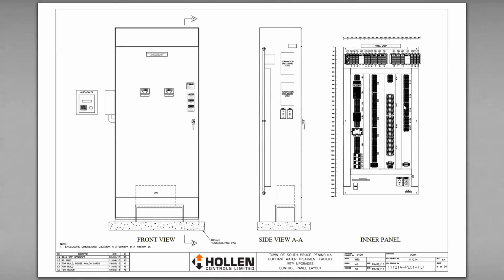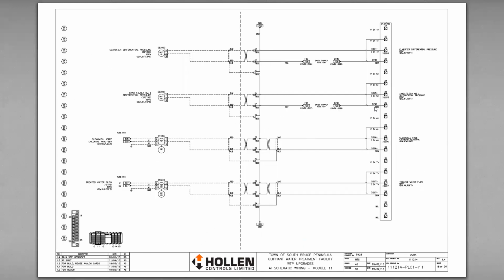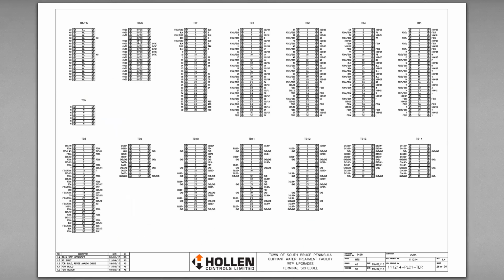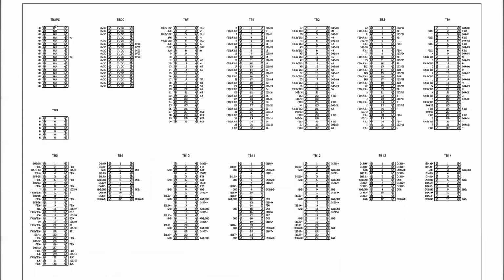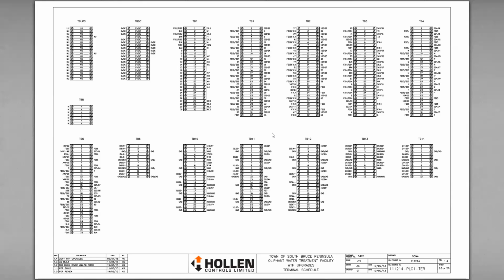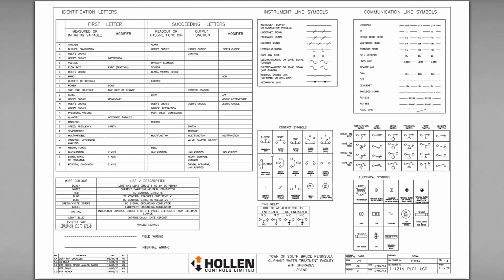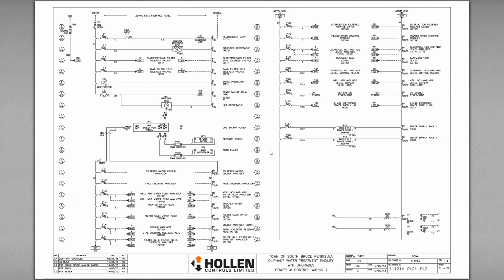At the back of this panel, this drawing set, these terminal blocks, I'm flying to the back on purpose. All of these terminal blocks here are labeled. So TB UPS, and then this should be what the label on the terminal block is, and then the wires and where they're all connected. So this would typically be, hopefully, something you would get back, should be inside your panel as an as-built. Sometimes you will never see a terminal block layout, or it could be penned in a whole bunch. Again, the more information you have about your panel before you need to troubleshoot it, the better.